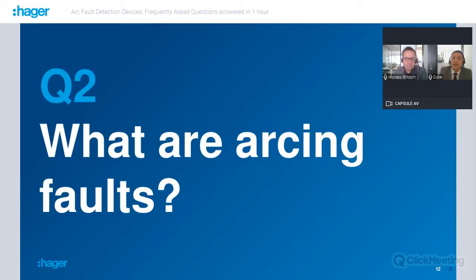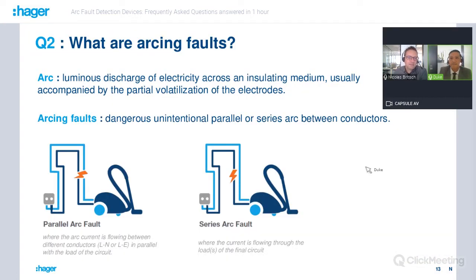So Nicolas, now we talk in the definition of AFDD about arcing faults. So what are arcing faults, please? Yes, it's also important to know exactly what an arcing fault is. So an arc, as defined in the standard, the 62606 product standard, is a luminous discharge of electricity across an insulating medium, usually accompanied by partial volatilization of the electrodes. And an arcing fault is a dangerous, unintentional parallel or series arc between conductors.